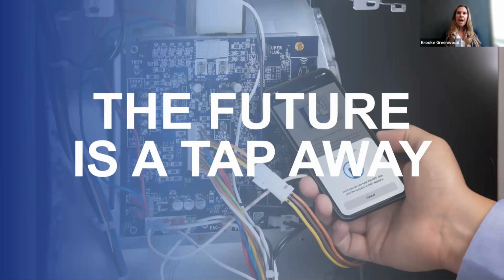You're going to tap the control board to pull information, make modifications in the Carrier Service Tech app, and then push information back to the control board using that same tap. You have to do that follow-up tap or none of that information will transfer. It's all point in time contact transfer of information. You've probably all used near field communication already, even if you think you're unfamiliar with it. If you've used Apple Pay, Android Pay, or Tap to Pay at the gas station or grocery store, that's all near field communication.